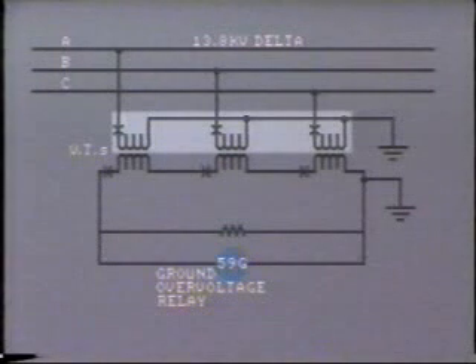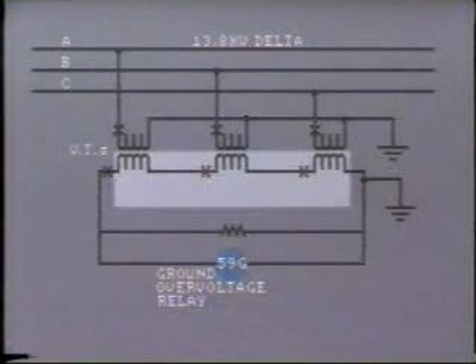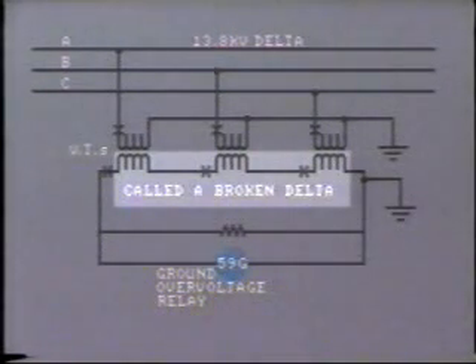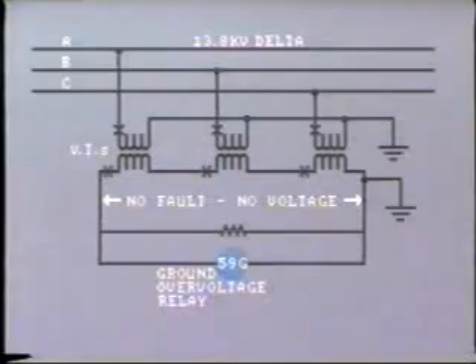This is, in essence, a Y-delta transformer. The Y-connected primary provides a neutral for the delta system, and this is solidly grounded. The delta secondaries of the transformer are connected in series. This is called a broken delta. One side is grounded like this, and the other feeds a ground over voltage relay.